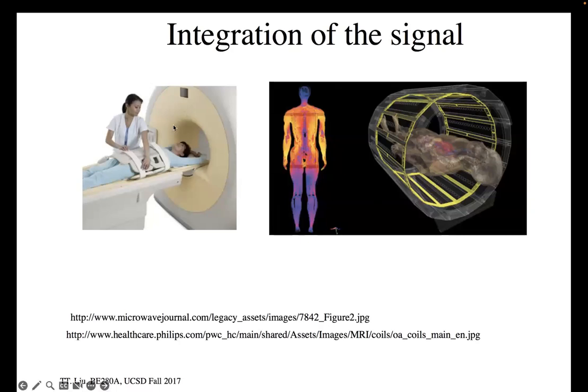Okay, so here we are again with the magnetic field. And this is a radio frequency receiver coil strapped around this patient's torso at this point. When the patient is rolled into the scanner, just inside the magnetic field windings is a thing called the transmit coil. And this provides the radio frequency energy that we're going to transmit into the patient. This design here is called a birdcage coil.